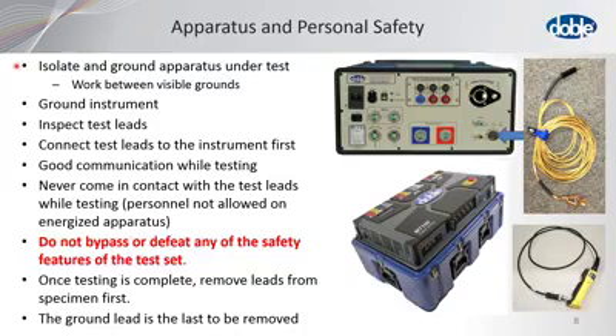You want to inspect the test leads to make sure that there are no issues with them, and connect the test leads to the instrument first, and then put them up on top of the apparatus before you run the test. Now, make sure you have good communication while testing. So in other words, like calling "coming hot" or "all clear," whatever is good for your particular crew, and make sure everybody understands the meaning of each one of the statements.